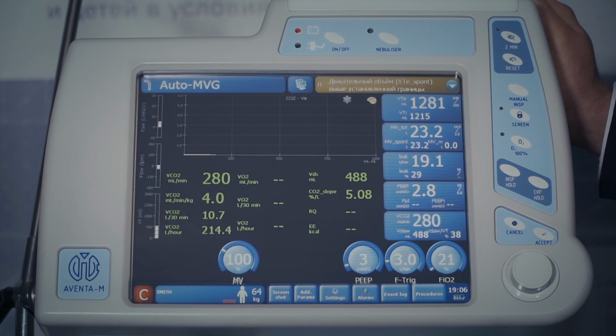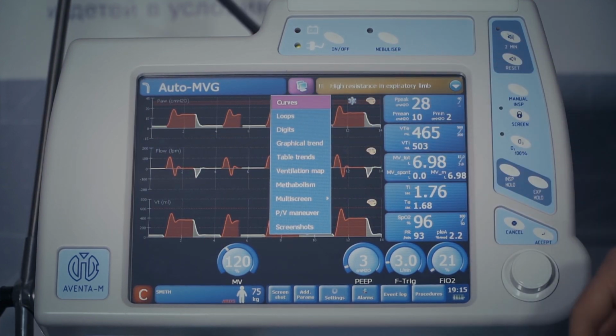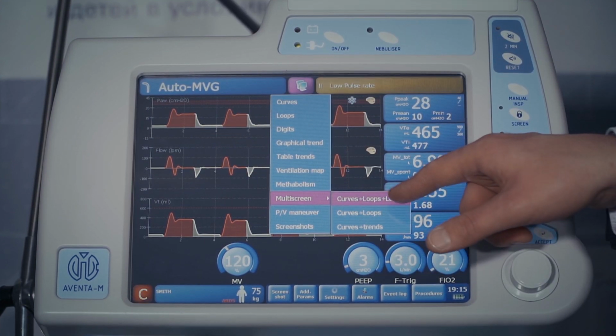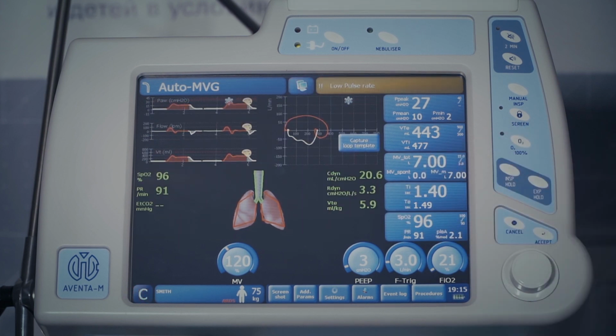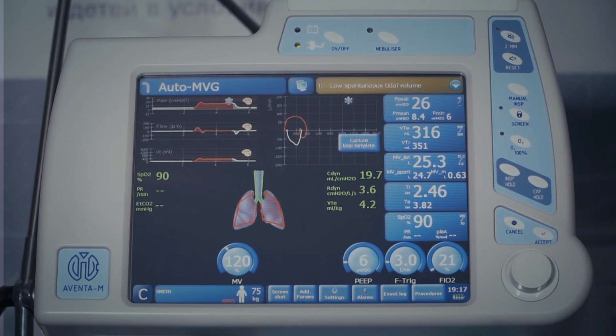Metabolism window allows to assess consumption and excretion of oxygen and CO2 during different time intervals, assess a patient's metabolism level and energy expenditure, which is very important for calculating of a patient's daily nutrition. The next group of run screens is merged under the common name multiscreen. It includes combined screens of curves and loops, curves and trends that combine the main screens described above.